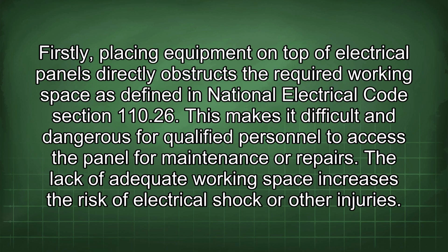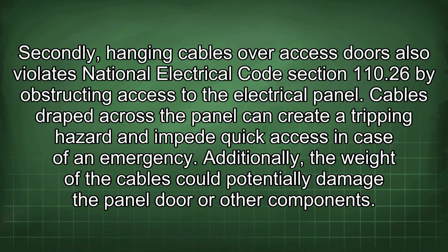Firstly, placing equipment on top of electrical panels directly obstructs the required working space as defined in National Electrical Code Section 110.26. This makes it difficult and dangerous for qualified personnel to access the panel for maintenance or repairs. The lack of adequate working space increases the risk of electrical shock or other injuries. Secondly, hanging cables over access doors also violates National Electrical Code Section 110.26 by obstructing access to the electrical panel. Cables draped across the panel can create a tripping hazard and impede quick access in case of an emergency. Additionally, the weight of the cables could potentially damage the panel door or other components.